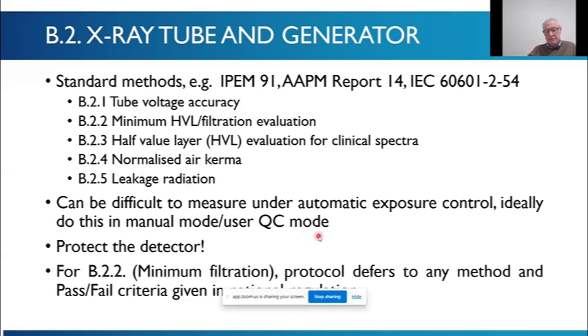These tests, we've done these for years, can be difficult to measure, as all dynamic imaging systems have AEC control, and these days it's very hard to turn the AEC off. Ideally, we'd want a manual mode or a user QC mode, and they are available on some systems, but few, and you may have to pay for those modes, or specify them at the tendering stage. So you need some tricks to be able to do this, where you take filtration and place it behind your multimeter to make the system change X-ray factors, so you can measure the kV and measure the yield, etc. at different tube voltages. And when you're doing this, it's very important to remember to protect the detector.